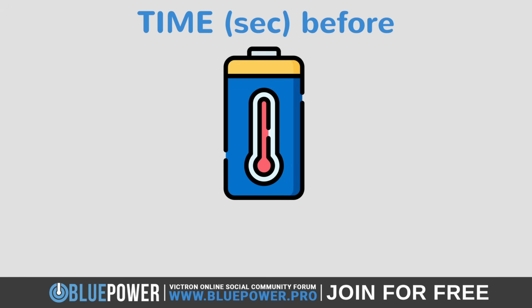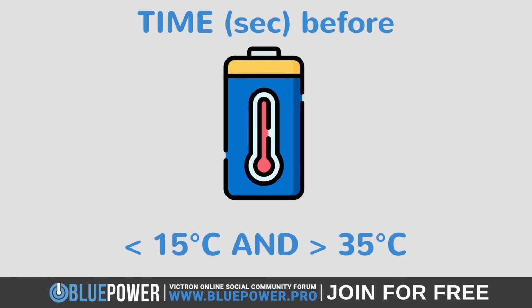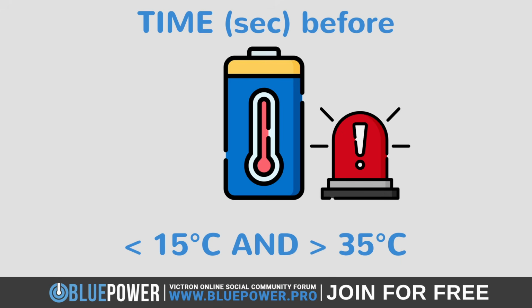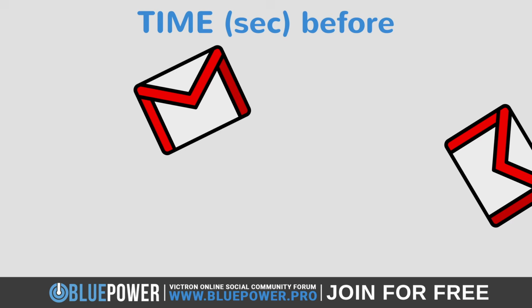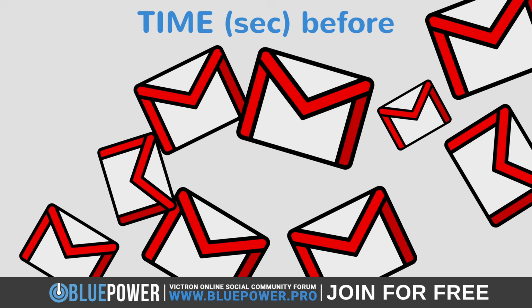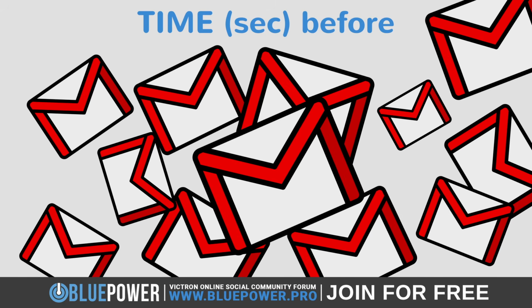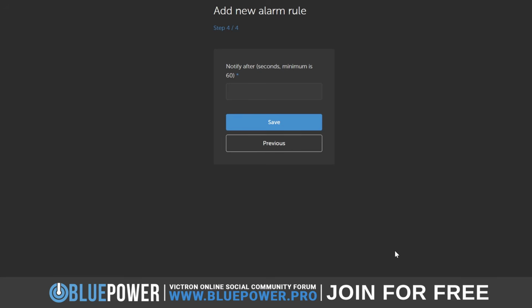Lastly, you want to set the time in seconds that the internal battery temperature must be either below the low setting of 15 degrees Celsius or higher than 35 degrees Celsius before a warning or alert is triggered. This is important to do in order to prevent yourself or others from being spammed by the system in the event of a quick spike or drop in temperature. You can set this as high as you want, with the lowest minimum being 60 seconds.